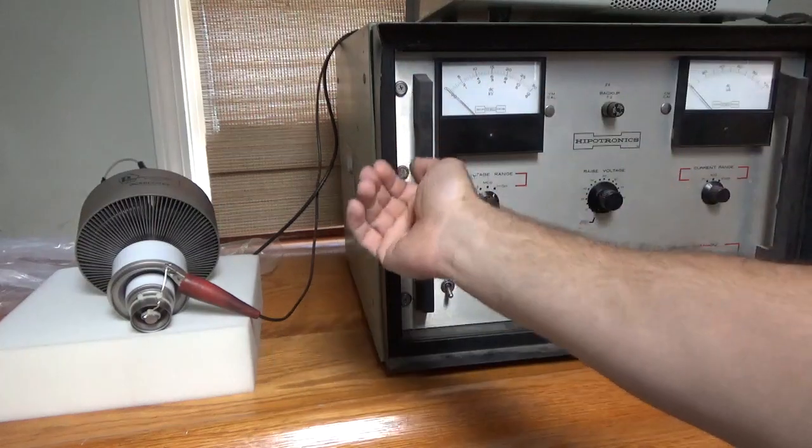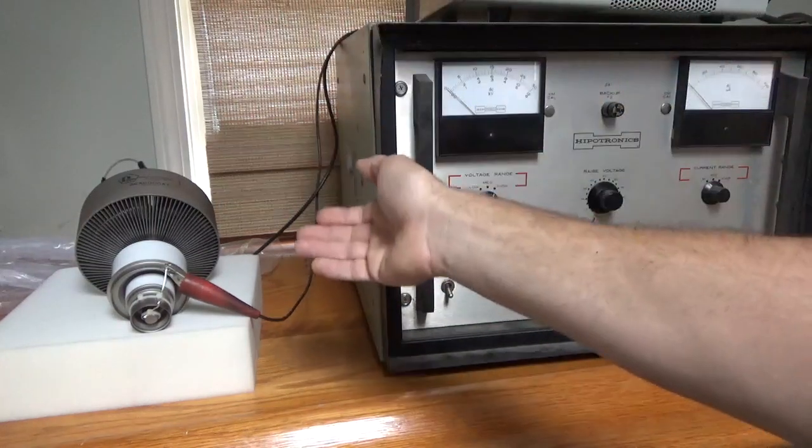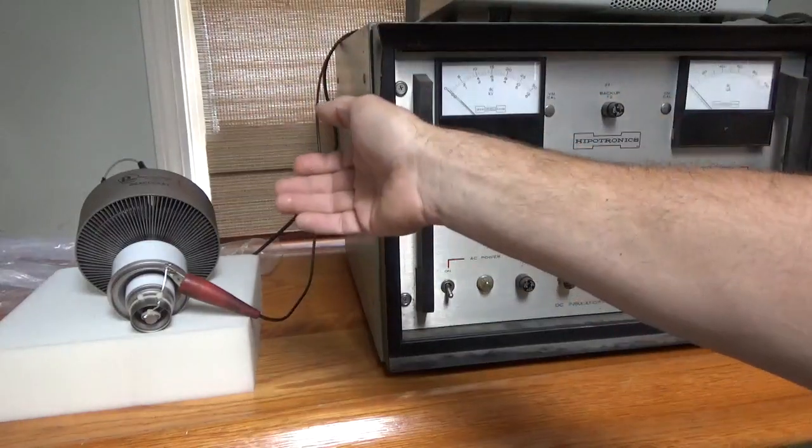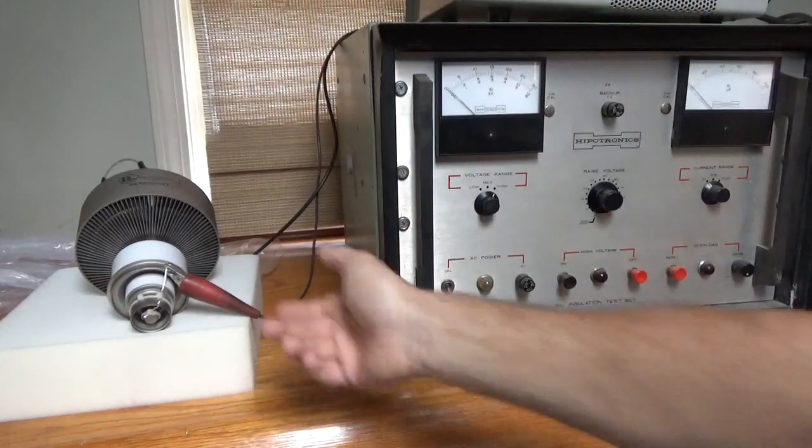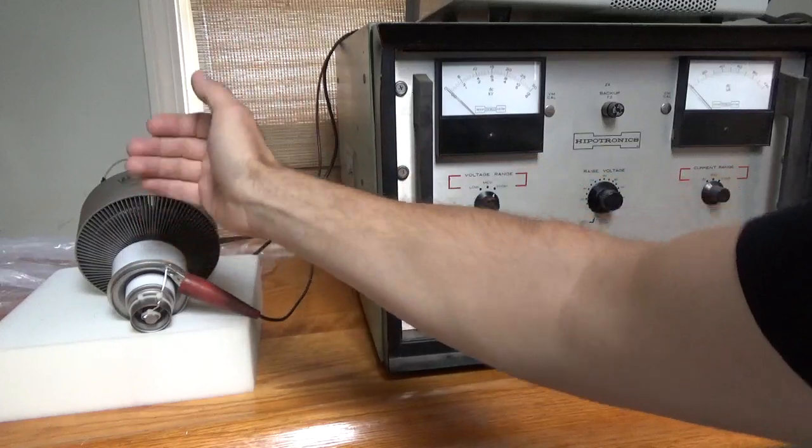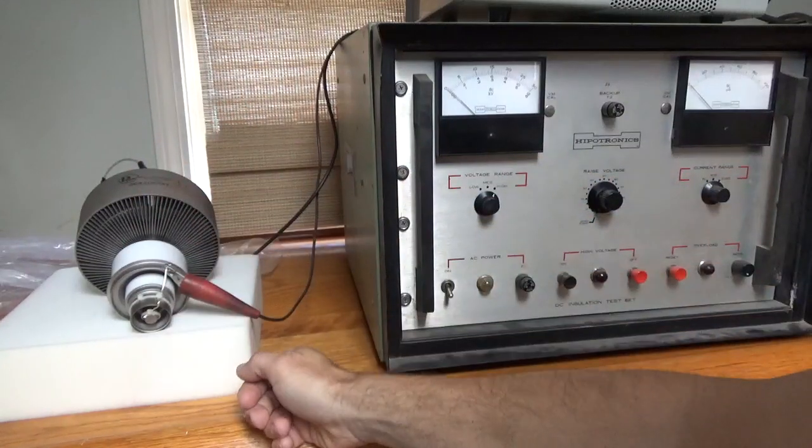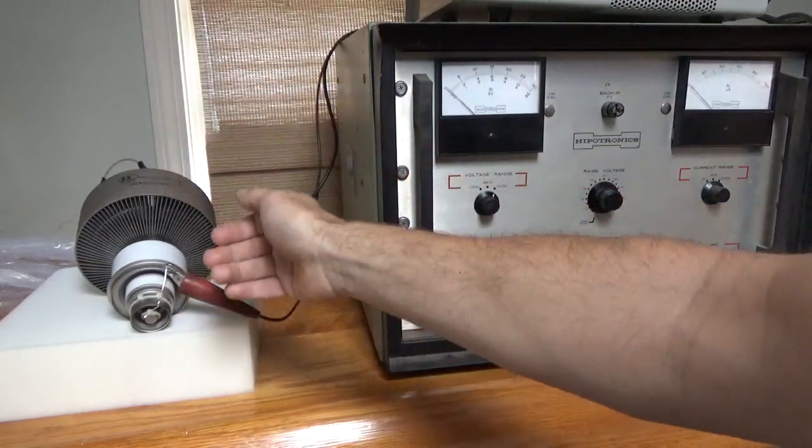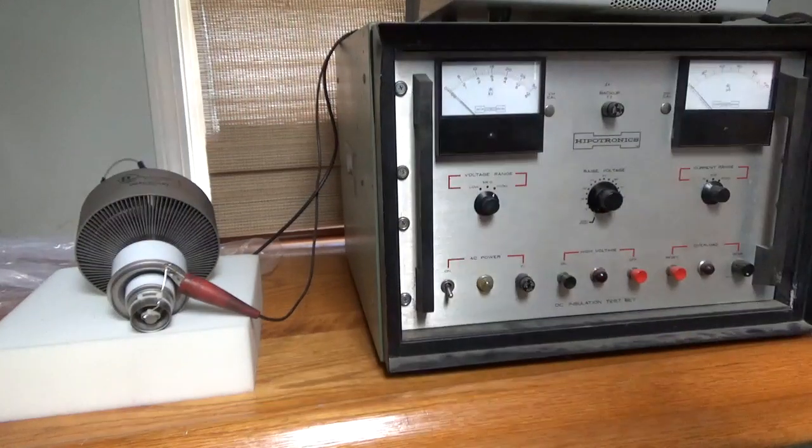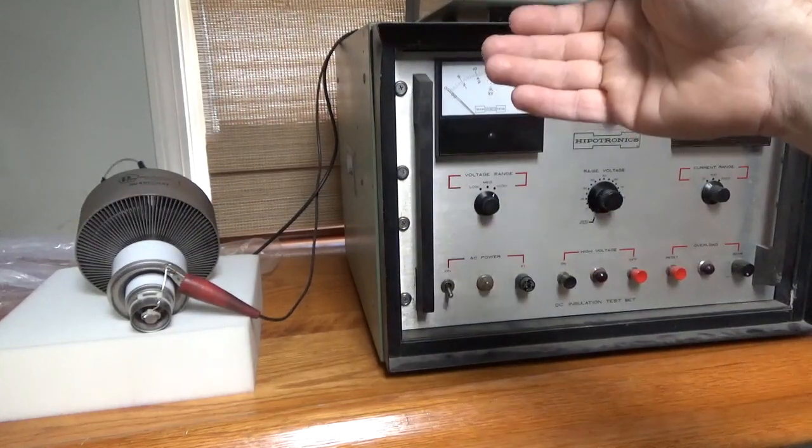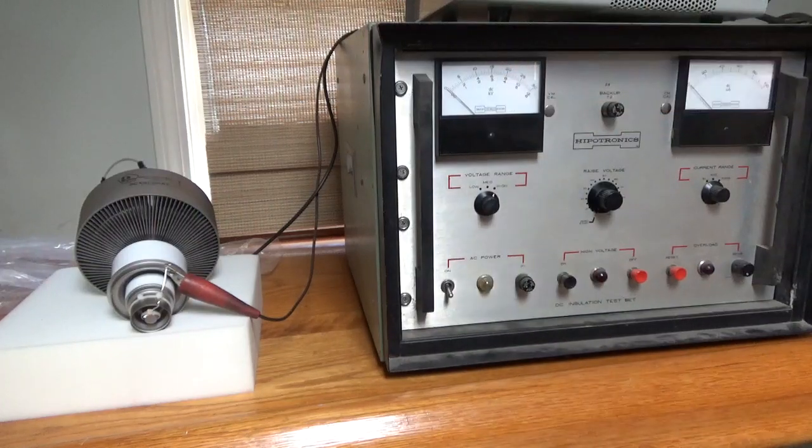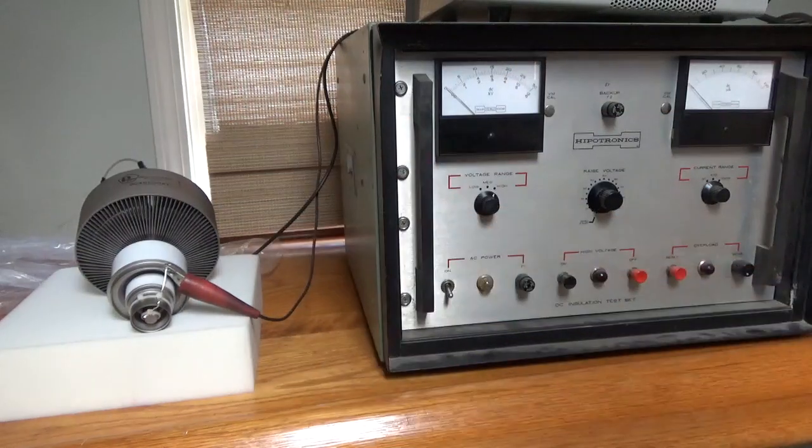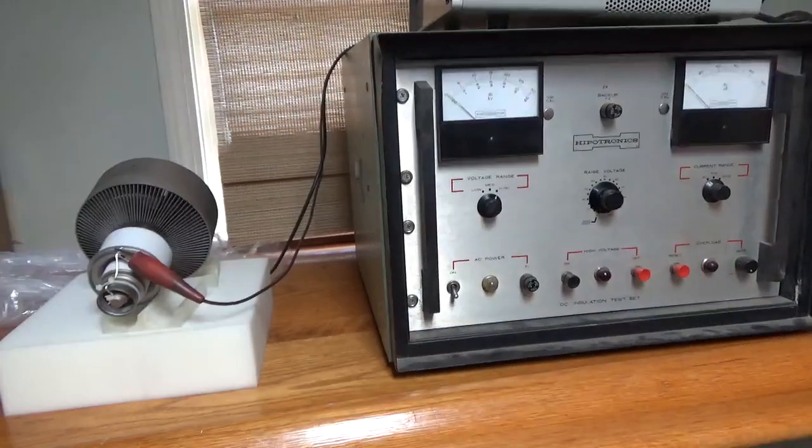But it passed that test in that polarity. I'll isolate it a little bit, redo the test, and then flip the polarity. And then I'll move on to the next test, which will be between the grid and the filament, which should hypot to at least 5kV. I'm going by what an engineer over at Conco since retired had told me for his specs. And then I'll also reverse the polarity. So I'll be right back.